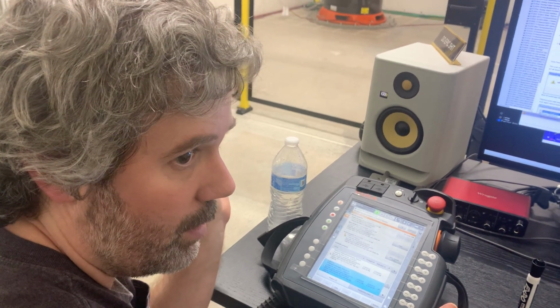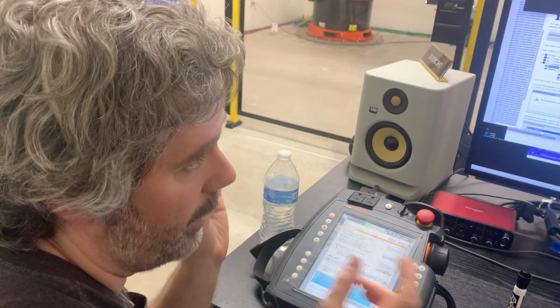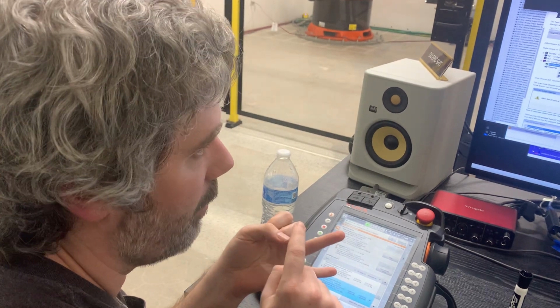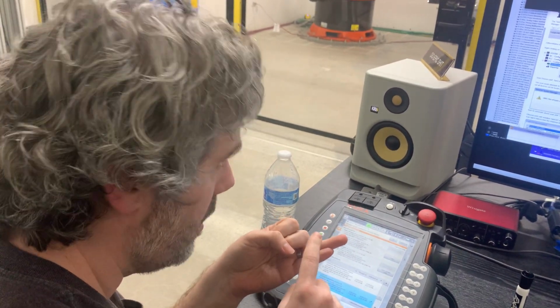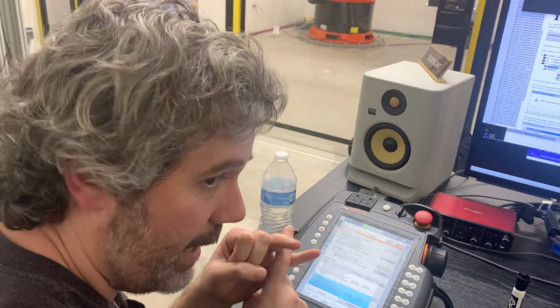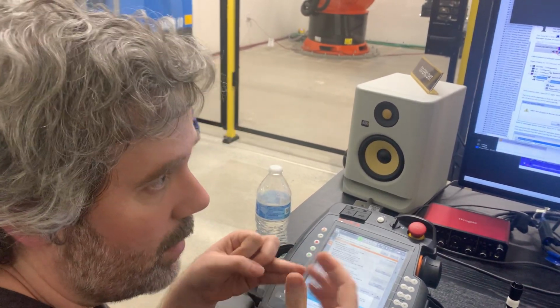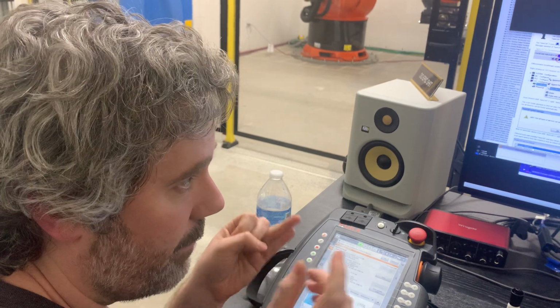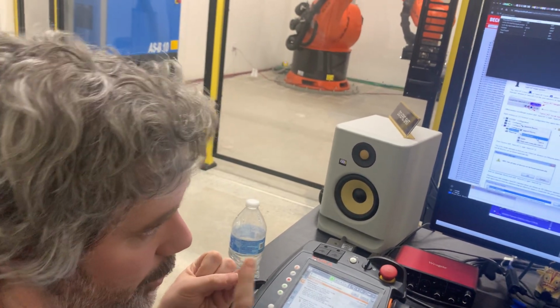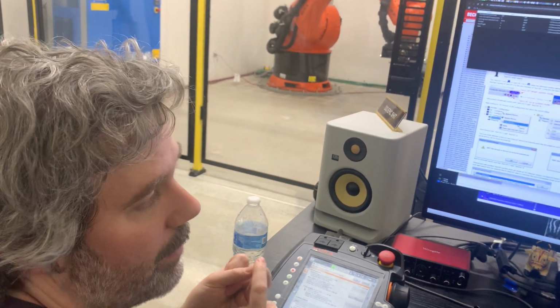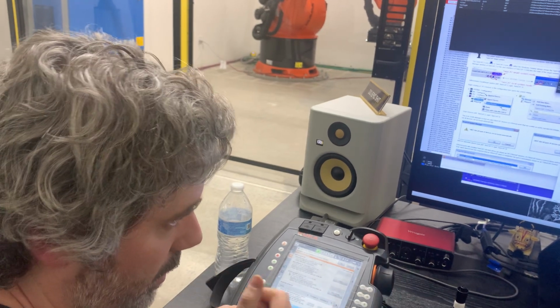So you can do hot changes. The caveat being there are things that prevent hot changes, which are memory restructuring actions. If you've added or deleted variables, you have to do a download. If you have just changed logic, then you can log in with an online change.